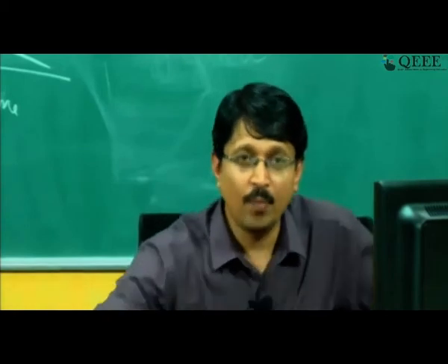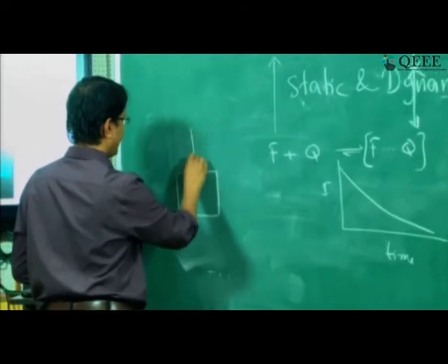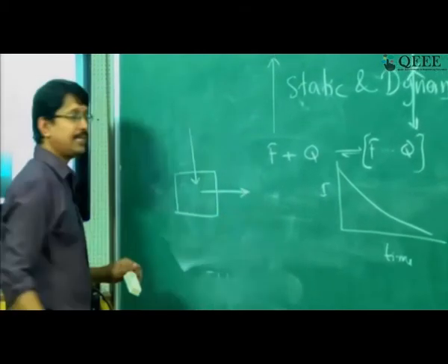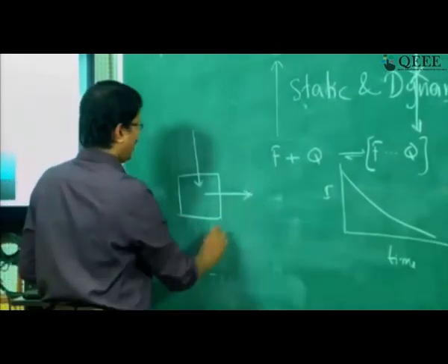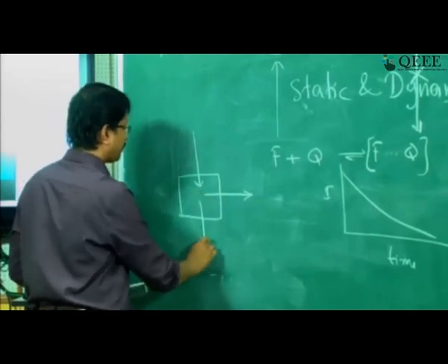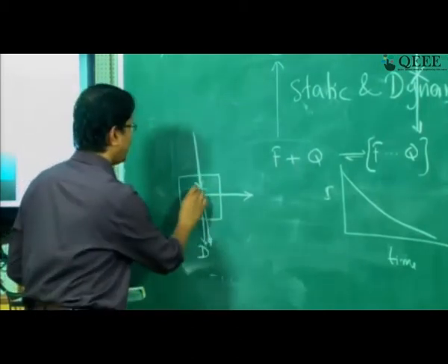That answer is, why there is an excited state, I mean why this configuration. The answer is very simple, because if you put the detector, we'll go to the board for a minute, in the sample chamber of the steady state fluorimeter, light is coming from here and the emitted light is collected at 90-degree. Why is that? Because if I put the detector here, then the emission light will come, on the top excitation light will also come, because here is my sample.